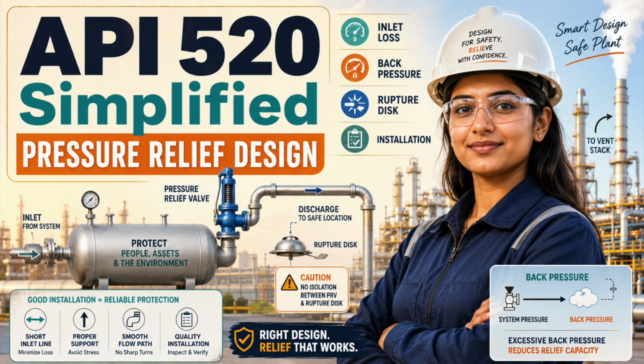The correct objective is not the largest possible valve. It is the smallest standard orifice that safely meets the required duty after all applicable corrections are applied. Good conservatism adds resilience. Bad conservatism creates another failure mode.